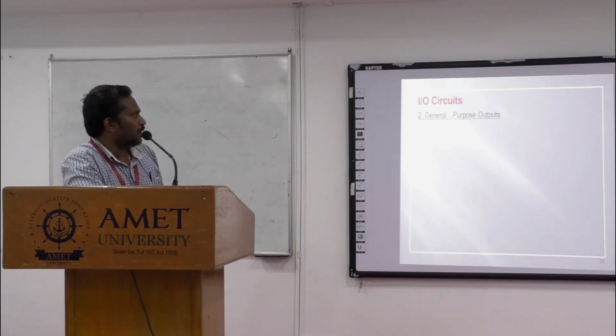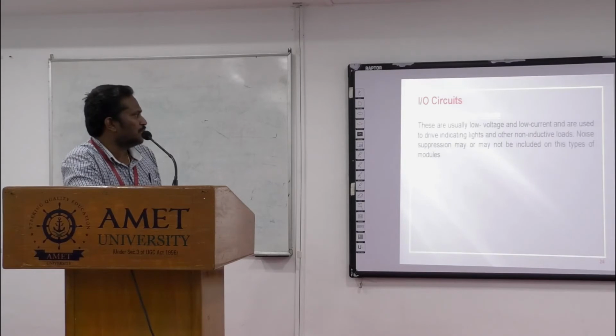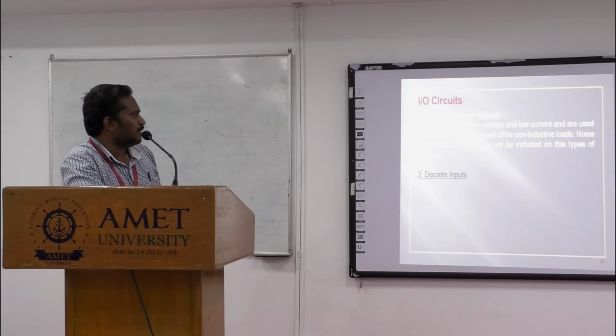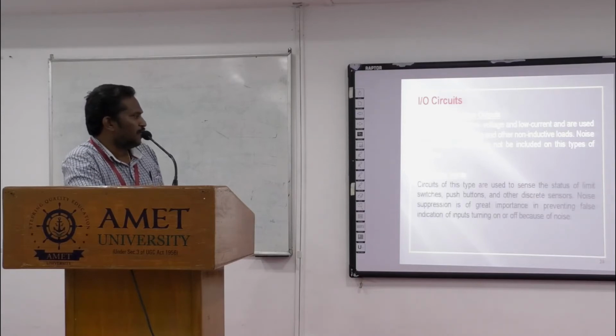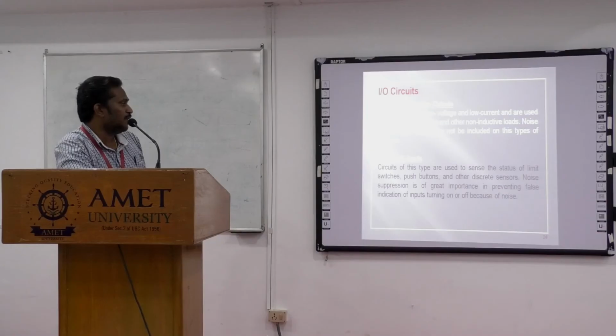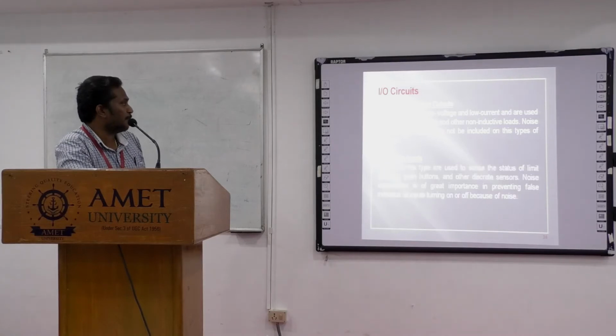The second I/O circuit is general purpose outputs. These are usually low voltage and low current and are used to drive indicating lights and other non-inductive loads. Noise suppression may or may not be included in this type of module. The third one is discrete inputs. Circuits of this type are used to sense the status of limit switches, push buttons and other discrete sensors. Noise suppression is of great importance in preventing false indication of inputs turning on or off because of noise.